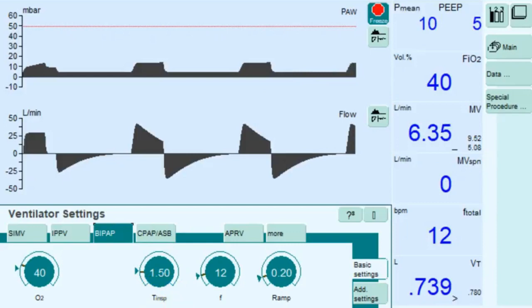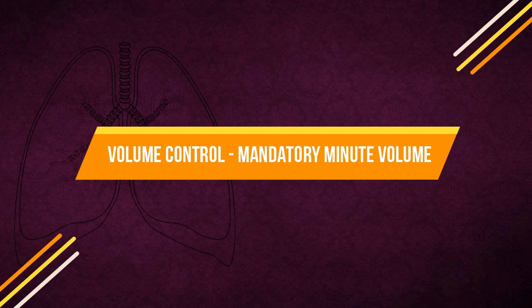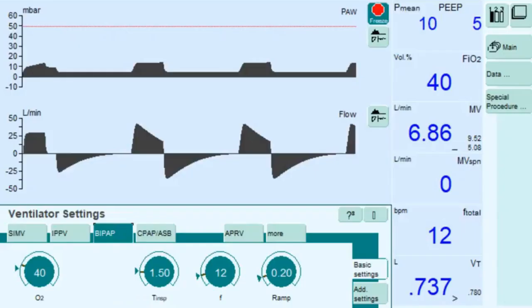The next mode is Volume Control Mandatory Minute Volume, which guarantees the patient always receives at least the set minute volume. The applied time-cycled, machine-triggered mandatory breaths are synchronized with the patient's breathing effort, and the patient can always breathe spontaneously at PEEP level. If spontaneous breathing is insufficient to achieve the set minute volume, machine-triggered time-cycled mandatory breaths are applied, synchronized with the patient's own breathing attempts.